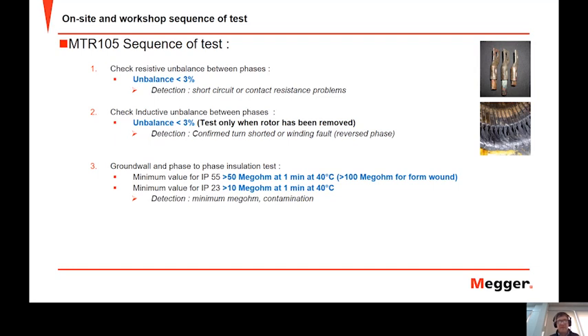Then we have our IR test and our PI test. This is looking at the ground wall insulation, and again can be used for phase to phase if we can open the neutral point. And this is where we're looking for a certain value of megohms. Ideally, for an IP55 machine, we would recommend greater than 50 megohms at 1 minute and at 40 degrees C. Remember that temperature correction. Or if we have a form wound winding, then we would say greater than 100 megohms at 40 degrees C. And then for IP23 machines, we would recommend greater than 10 megohms at 1 minute, again at 40 degrees C. And we're looking here for contamination, moisture, and even potentially damaged insulation.